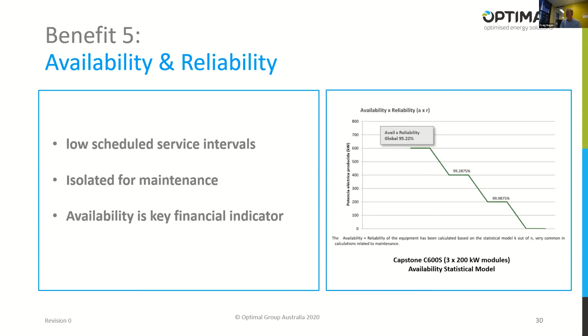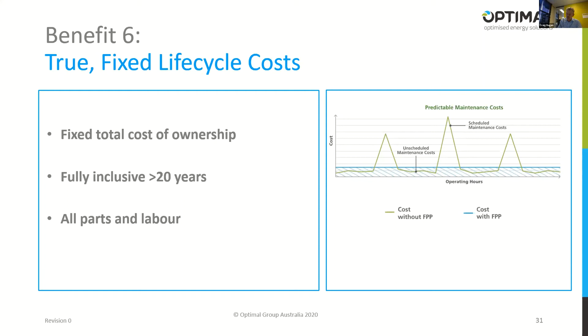One of the other things that we do is put most of our customers on a factory protection plan, which is a 10-year or 20-year fixed cost maintenance plan. So you pay a fixed cost per annum, and we do all the maintenance, scheduled and unscheduled, over the period of that FPP, and that includes all parts and all labour. That includes at 40,000 hours, as I said earlier on, we change the power head, and we repeat that every 40,000 hours. At 20,000 hours, we replace the injectors, and there's a whole bunch of filters and other bits that we're regularly replacing. So typically those components aren't failing and they're being changed before they fail, so we have very, very good uptime.